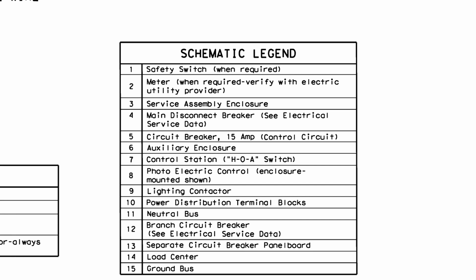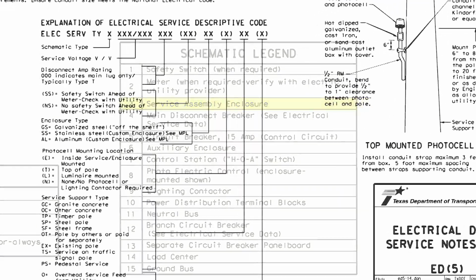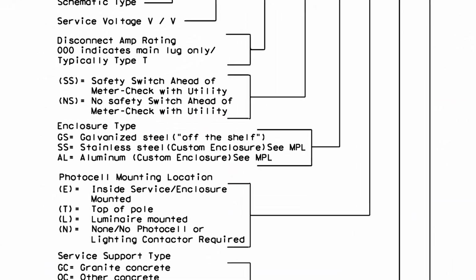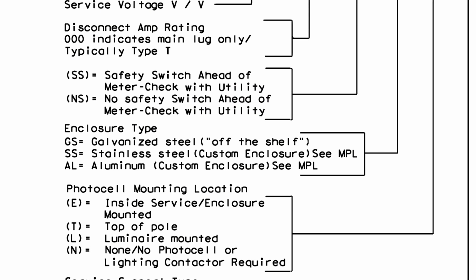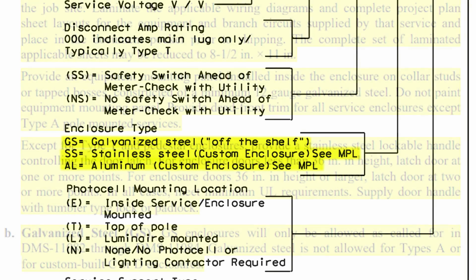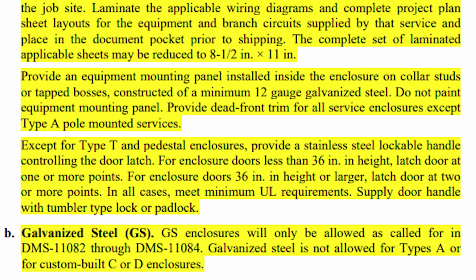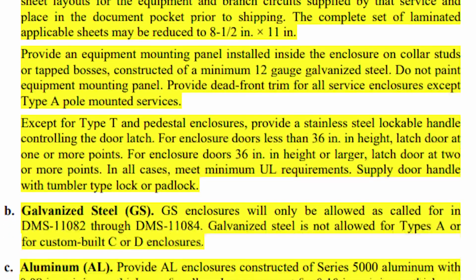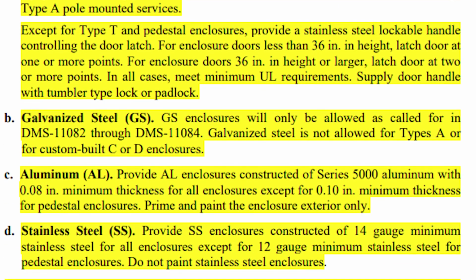First, we will inspect the service enclosure, noted on the drawing as Item 3. The explanation of electrical service descriptive code on ED5 shows enclosure type options of galvanized steel, GS, stainless steel, SS, or aluminum, AL. TxDOT's Departmental Material Specifications, DMS 11080, for electrical services, does not allow Type A enclosures to be made of galvanized steel. Therefore, a Type A service enclosure may only be made of aluminum or stainless steel.